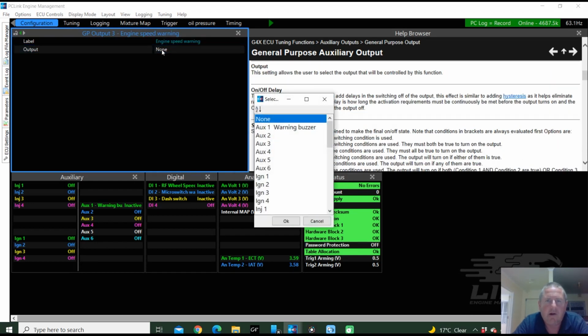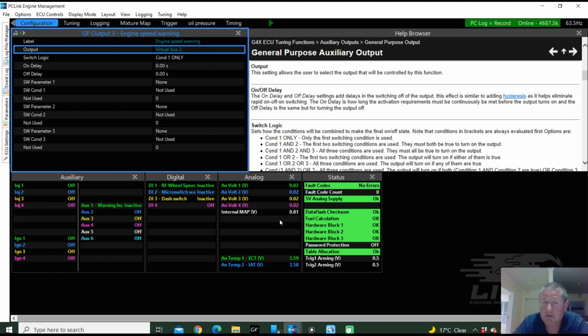Virtual auxiliary number 2 - there's a lot to remember when we're doing this. So we want it to give us a warning if the drive shaft or the engine RPM front drive shaft is going too slow. I'm just going to leave it on condition number 1. I'm not going to worry about a delay on or delay off. I've got a delay set in the real auxiliary.